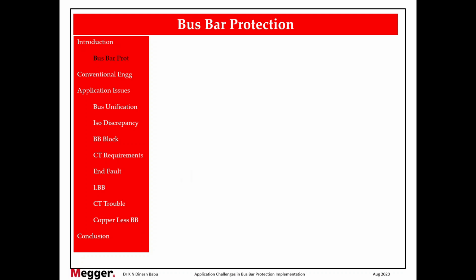What is LBB? So LBB we know, but what kind of issues can occur in LBB? And CT trouble. So what is the trouble in having CT trouble? So should we really have CT trouble? Should we block busbar or should we permit the busbar to trip?